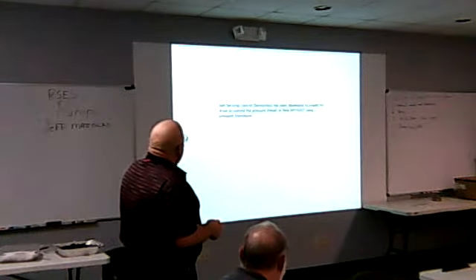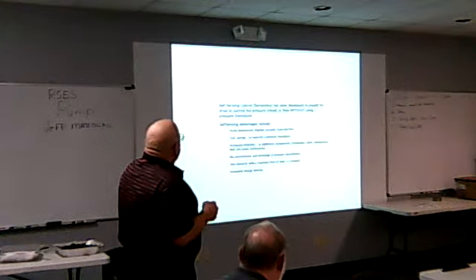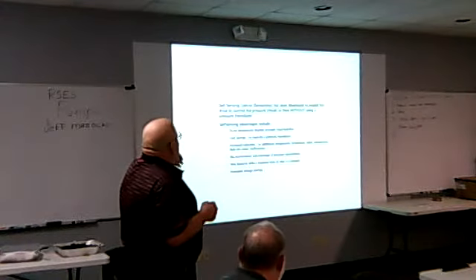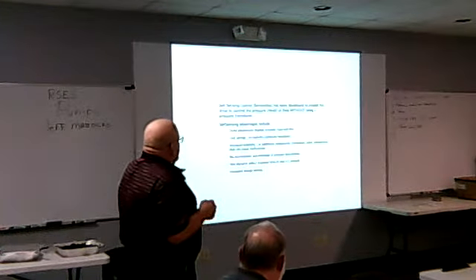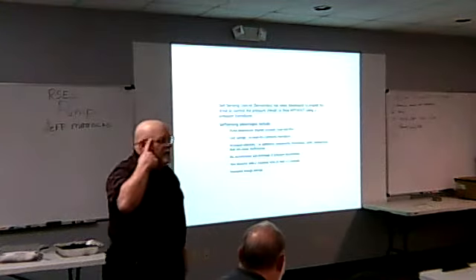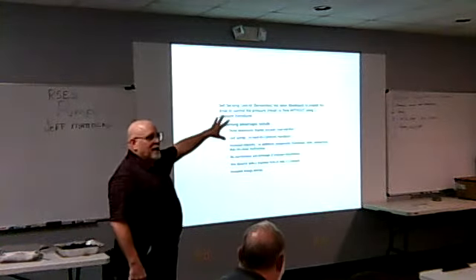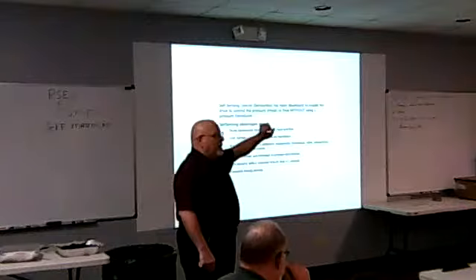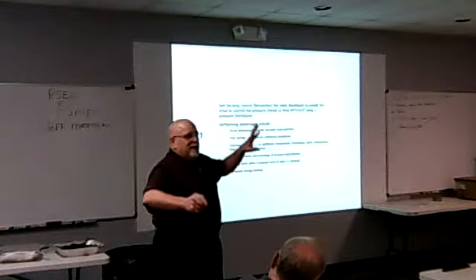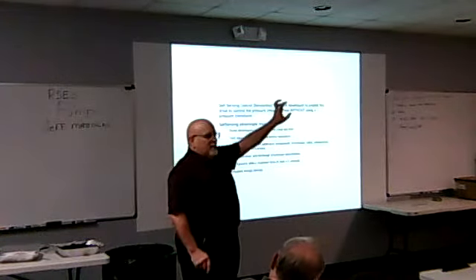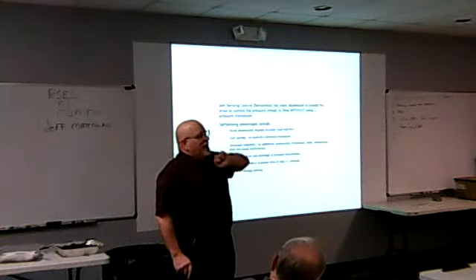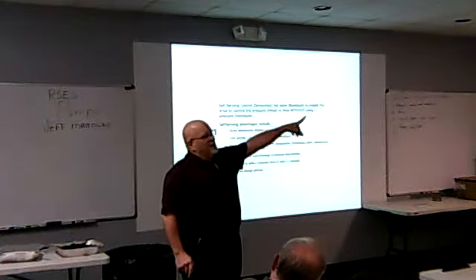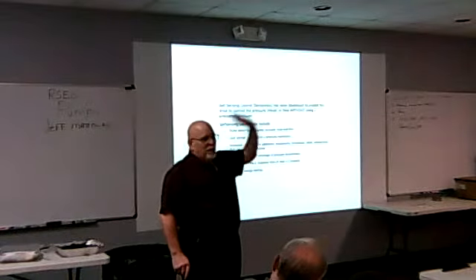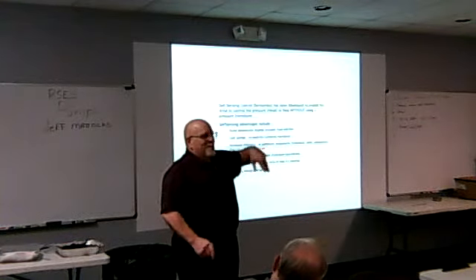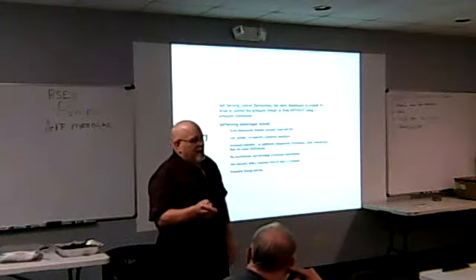And the way they work, your drive will tell you what flow and head you're at. You start these, there's no DP. Normally in a VFD system, I've got a DP two-thirds of the way out in the system set at 3 or 4 PSI. As my 2 and 3 ways kick in and out, I'm changing the flow of my system, the VFDs are ramping up and down. But I have to have a control system that looks at this DP and samples it every 10 seconds. Way out, I got 100 feet of wire out there, blah, blah. These do away with all that. Magic.